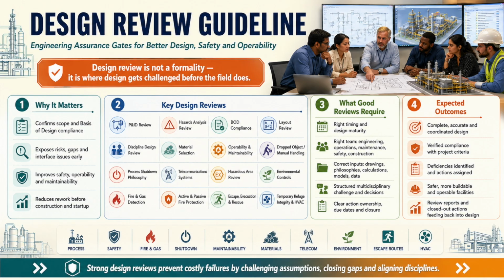initiate the correct response. Active and passive fire protection reviews test hydrants, monitors, foam systems, deluge systems, water mist, inert gas systems, fire water networks, passive protection, water curtains, package systems, fire pumps, foam pumps, valves, routing, isolation, redundancy, vulnerability, hydraulic adequacy, surge effects, accessibility, initiation, and emergency power. You examine whether the system complies with the safety philosophy and whether deviations provide demonstrably equivalent protection. A fire protection system that is inaccessible, vulnerable to the same event it must control, hydraulically inadequate, or impossible to maintain is protection only on paper.